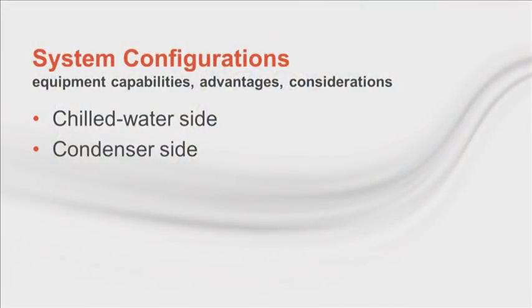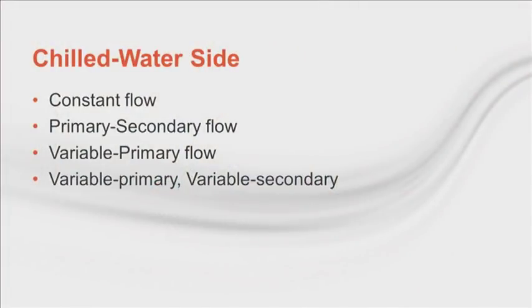We're going to divide these further by system configuration, as that affects how our plants are controlled and optimized. We'll start with the chilled water side and then go to the condenser side, always mindful that chillers see the effects of both. Historically, there's been a progression in design, from constant flow to primary-secondary flow to variable primary flow. Some, especially existing chiller plants, have migrated to a combination that varies the flow through the chillers and the secondary loops at the same time. The configuration that you have determines which energy saving strategies are possible and suitable.